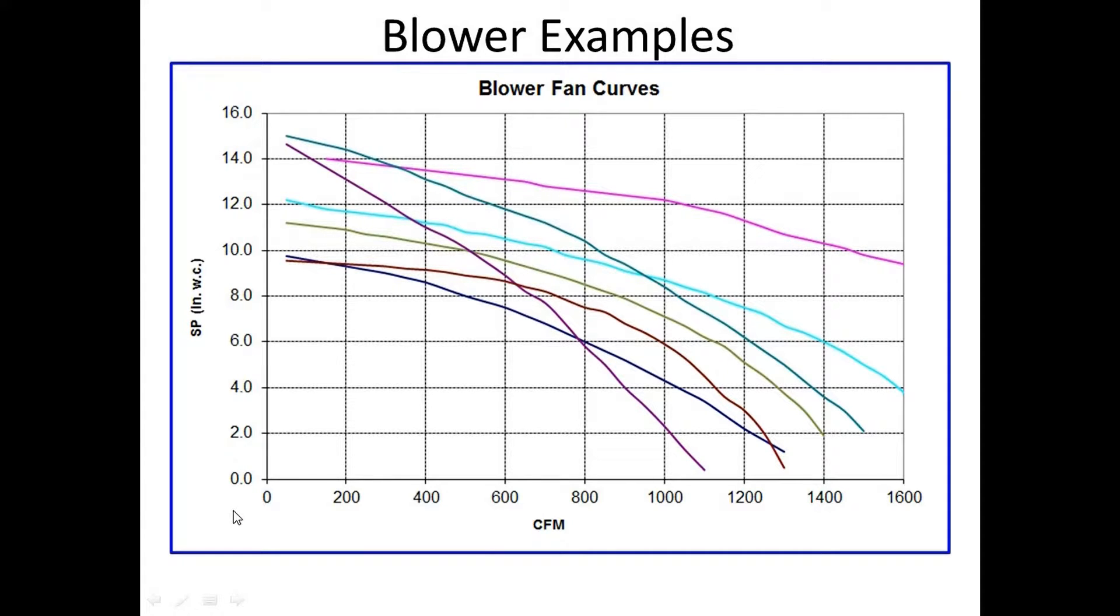One of the things you need to be aware of is that a lot of the units, they'll sell a unit that says, 'Oh, I can do a thousand CFM on this unit and it will do up to say 14 inches of water column static pressure.' What they don't tell you is it won't do those both at the same time. The truth is it curves somewhere in between.